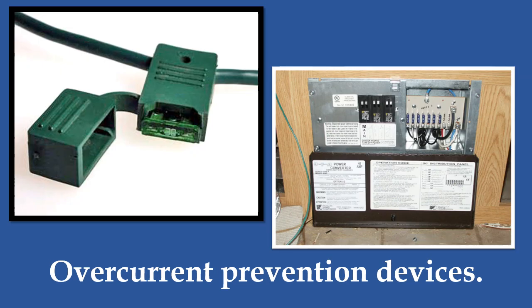Blade type fuses provide overcurrent protection either from individual inline fuse holders as seen here on the left, or, as in the photo on the right, contained in the 12 volt distribution panel side of a combination load center. When either fuses are blown or circuit breakers are tripped, current is cut off to the downstream circuits that they protect. Fuses will always need to be replaced, where a circuit breaker simply needs to be reset.